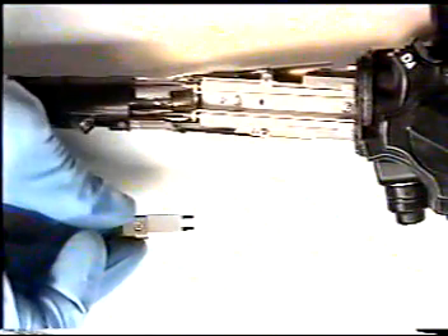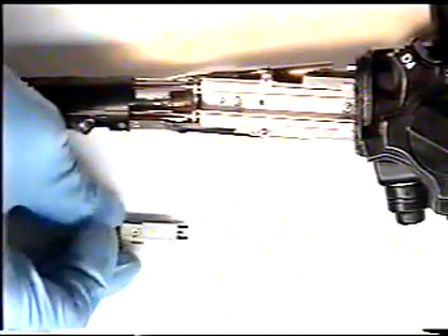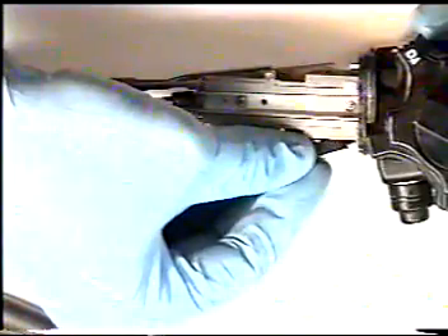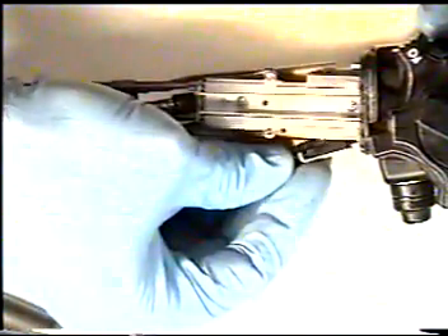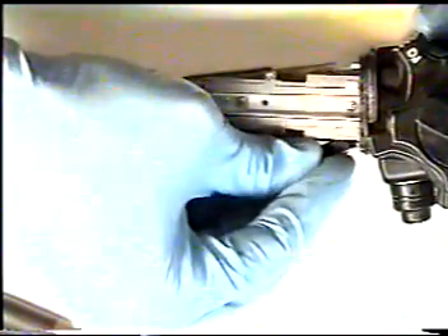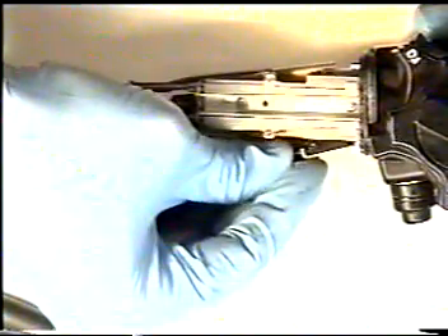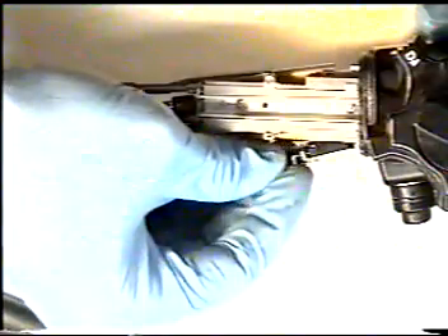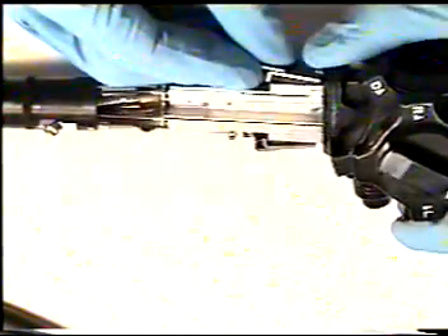Next step is to insert the angulation block. First step is to loosen Phillips screw. Do not take it all the way out. We were just loosening this up. There are two posts at the end of angulation block. These fit in internally to the control body at a 45-degree angle. The two slots will meet the two holes inside body section. Once it is inserted in, push the block flush up against the body. Again, lining up block with holes internally, slide it in, pushing it flush up against the body.